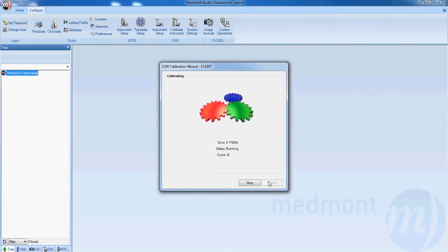This same calibration procedure can be used with each calibration that's required over the course of the life of your instrument. Every 6 months approximately, the instrument should be recalibrated. It should also be calibrated if it is bumped or jarred in such a way that you might be concerned about the accuracy of the unit. This concludes the video on calibrating your Medmont E300 corneal topographer.